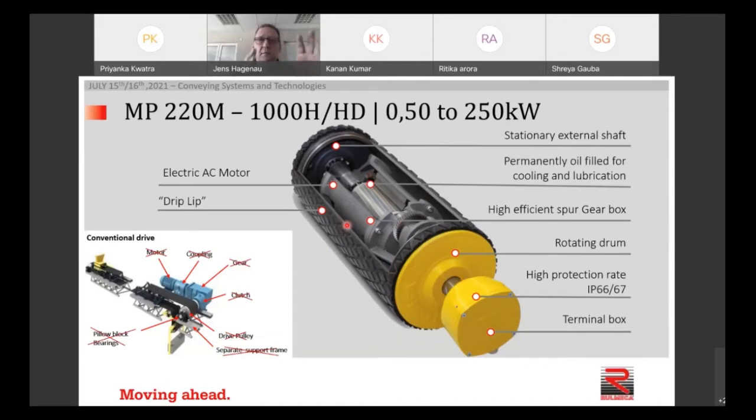All these components, motor, gearbox, and the connection to the pulley, are directly connected. There is no extra coupling inside. That means, especially for bigger motors, for bigger powers, in case a smooth start is required, the starting will be provided by the electronics, that means by a frequency converter or maybe a kind of soft starter. This is not realized by any specific coupling.